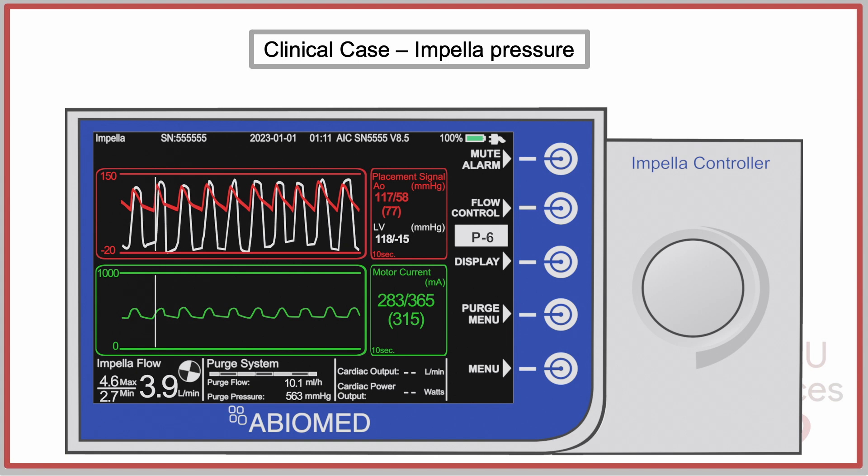This was the device screen the day after implantation. It was set to P-Level 6, generating a flow of approximately 4 liters per minute.